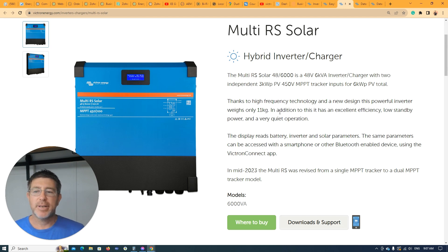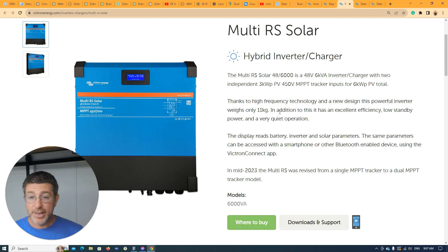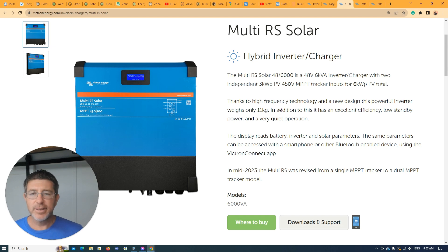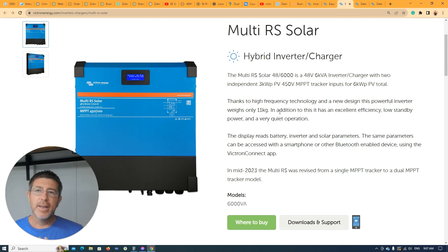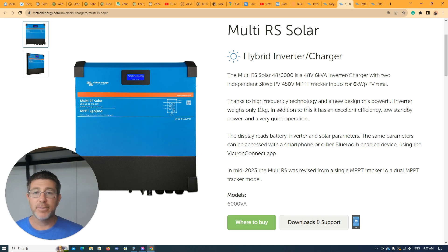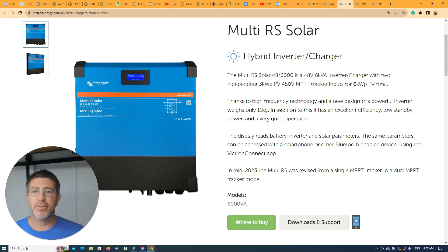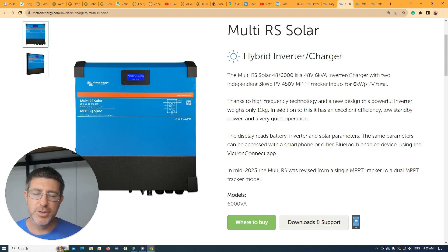The other great thing about these is because they're using Victron's high frequency technology. There is an upside to that. They're a lot lighter, and you're getting a 6kVA inverter compared to a 5kVA inverter on the Easy Solars. So you're getting a little bit more grunt out of them. One downside with this, you can't parallel them. So on a single phase, you can't have a 6kVA and a 6kVA on that same phase, but you can actually use them in a three-phase situation. So you can have one on each phase in a three-phase and get them to all work in a three-phase situation, which is great.